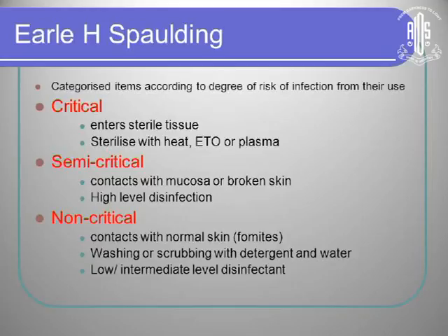Items are classified into critical, semi-critical, and non-critical. Critical instruments are those that enter sterile tissue, like scalp veins — they are sterilized with heat, ETO, or plasma. Implants and IOLs are also critical; you cannot just disinfect them, you must sterilize them. Semi-critical items contact mucosa or broken skin and need high-level disinfection. Non-critical items contact only normal skin.